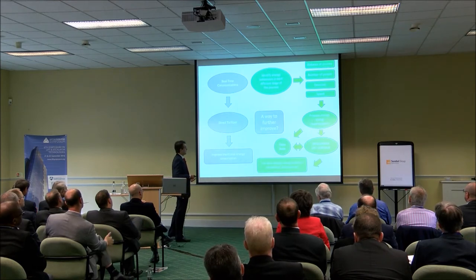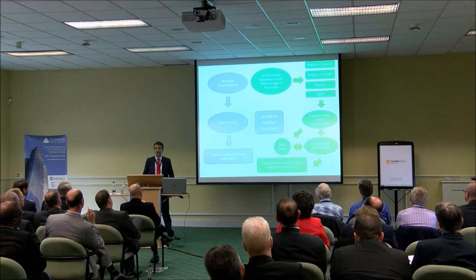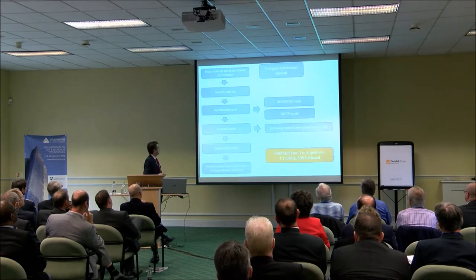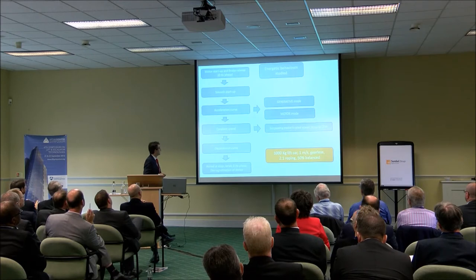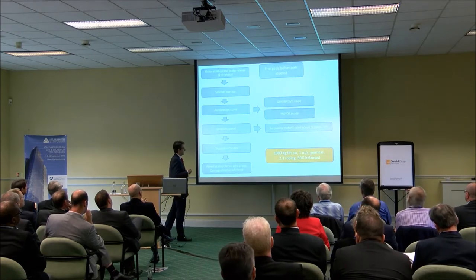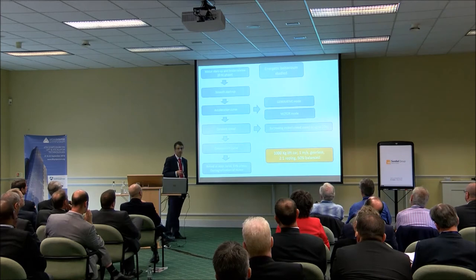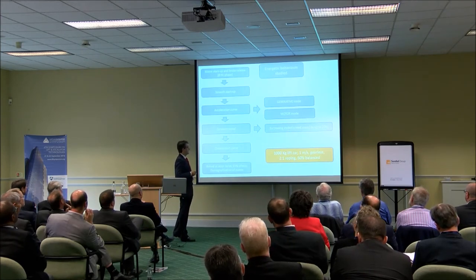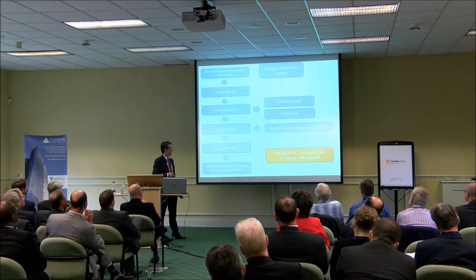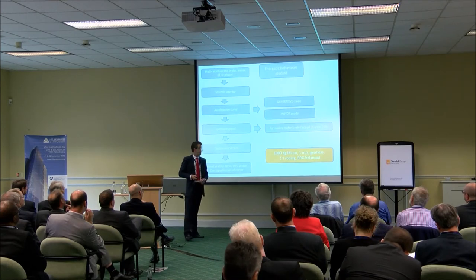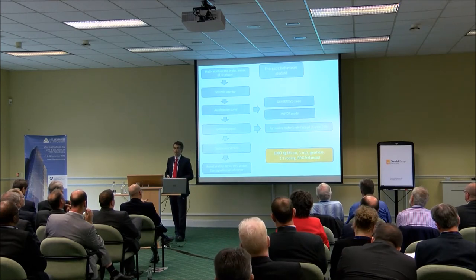We would like to choose the best energy saving profile for each journey. We have studied the different stages and different energetic behaviors, all of them in more than 500 tests carried out in our test tower. We have installed a lift of 13 people capacity, 1 meter per second, gearless 2-to-1 roping, 50% balance with a compensation chain.